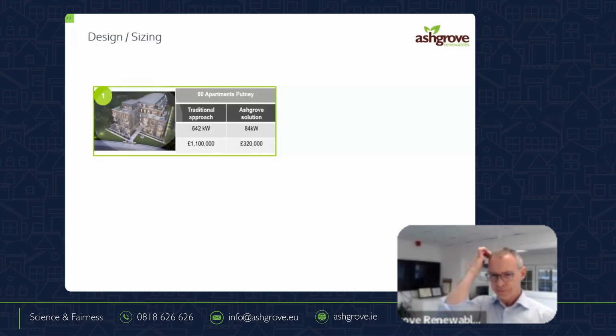So we're into design now. We're going to talk about the things that maybe have hindered large heat pumps for the last 20 years. One of the first projects Johnny and I did in England at scale was a block of apartments where the consultants had used sizing philosophies that were fine in the past. If I was sizing a gas boiler, it didn't really matter if it was 200 kilowatt or 500 kilowatt, it went up maybe 10,000. In our world with heat pumps, 200 kilowatt to 500 kilowatt is hundreds of thousands. So we really need to understand, do we need big heat pumps or can we get away with something smaller?